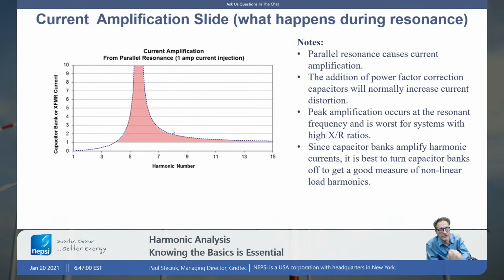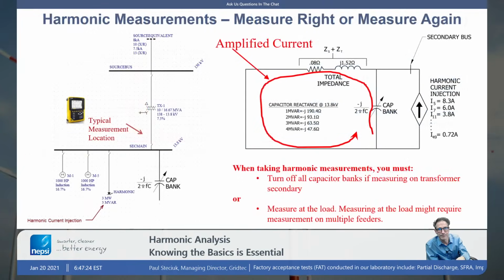That current amplification is flowing in the capacitors, it's flowing in the source impedance. So if you have a harmonic standard at the point of common coupling that involves harmonic current, you're going to easily exceed the standards if you add capacitors to the network. So oftentimes adding filters is the better thing to do. The other thing is the capacitor current will go up, which means that we may operate fuses within the capacitor.